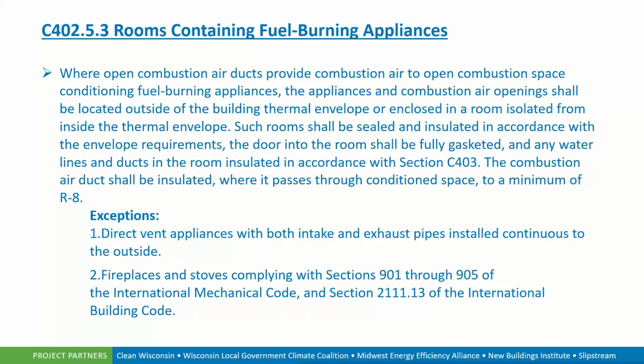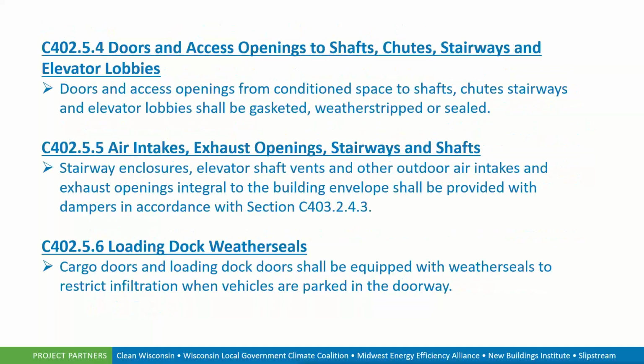You have direct vent appliances with both intake and exhaust installed continuous to the outside. So a direct vent furnace where the intake and the exhaust both go to outside. And fireplaces or stoves that comply with the IMC or the IBC section of the code. So just be aware that there are additional requirements when we have those to provide combustion air openings and separate those spaces or those appliances from other areas of the dwelling.